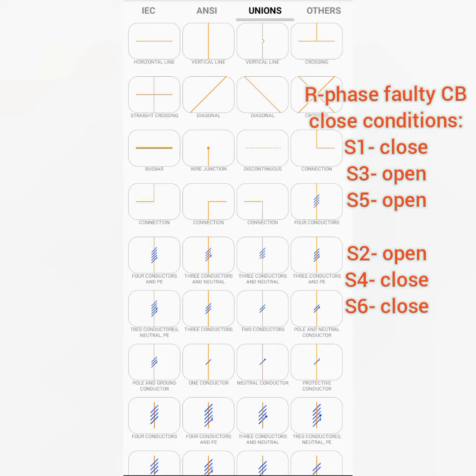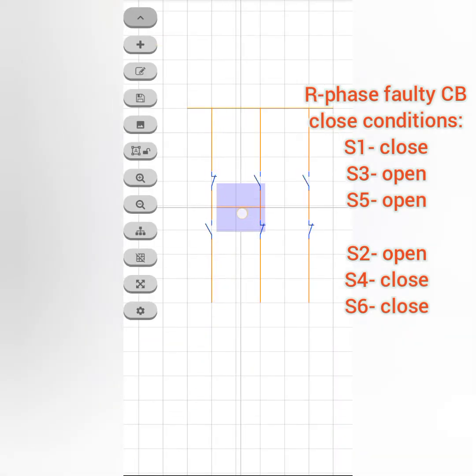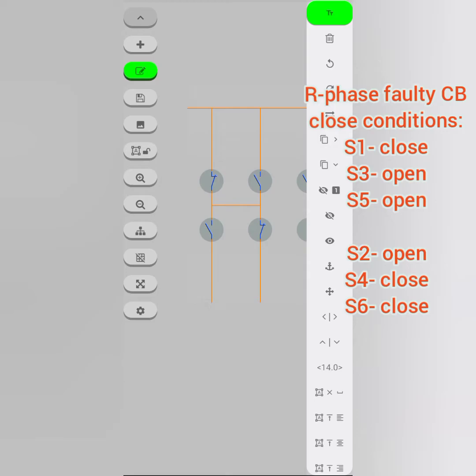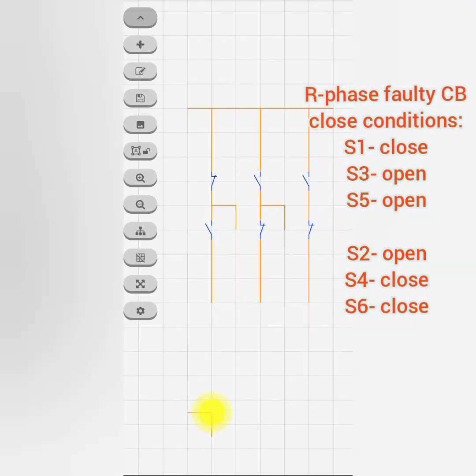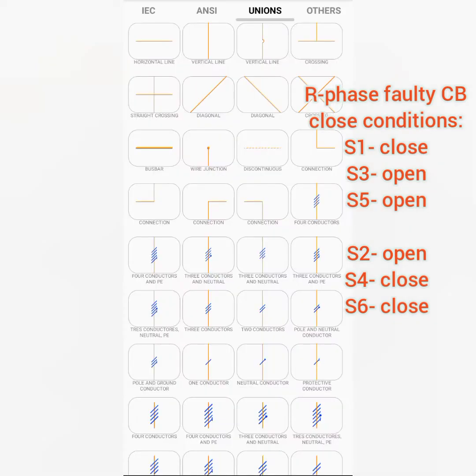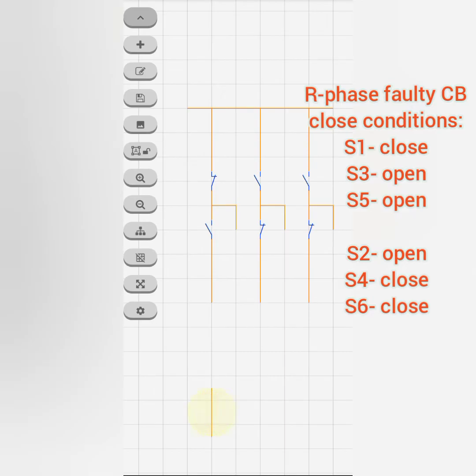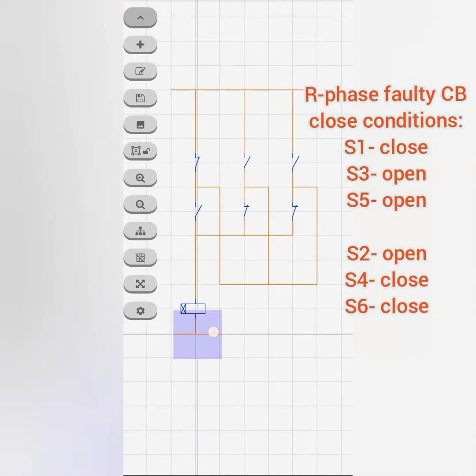This is how the timer connections are arranged. Since the R phase is faulty, the positive terminal coming from S1 is connected with all three parallel S4 and S6 connections. Automatically the positive will move to S4 and S6 and then reach the timer. On the timer side we have a negative, so automatically the timer will get initiated in this condition.